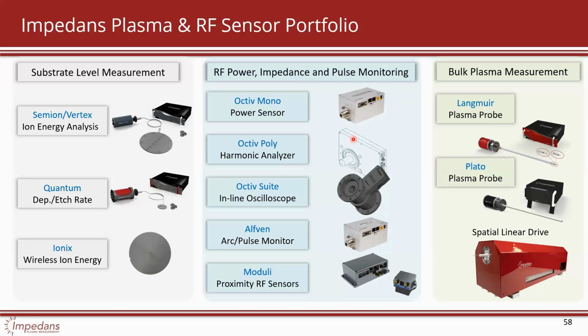One thing you have to keep in mind: if you have a plasma that's powered by pure DC, like DC magnetron sputtering, you have to keep an eye on what kind of current you're providing to the plasma. We've actually seen situations where people were trying to measure a plasma where their DC power supply had, let's say, 100 milliamps. They had a Langmuir probe in and were trying to collect Langmuir probe data, but the data didn't make sense.